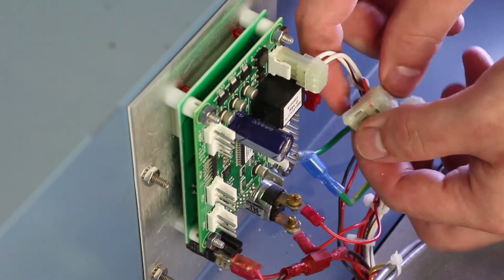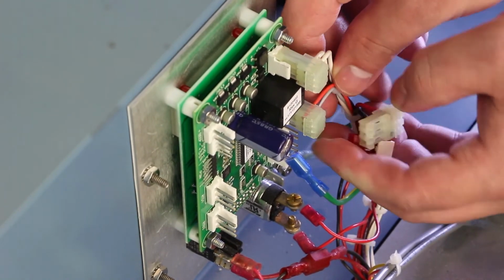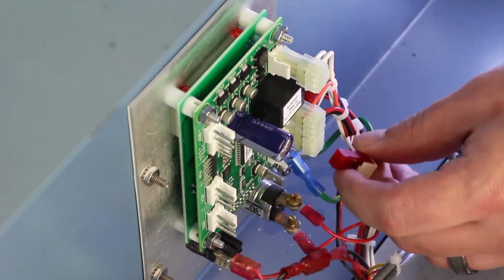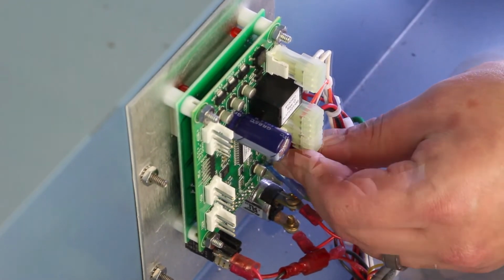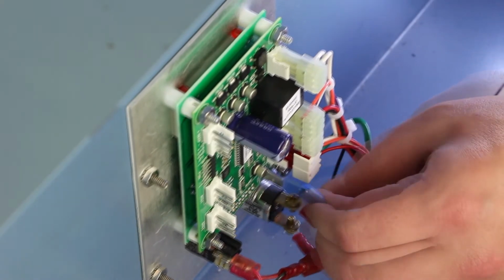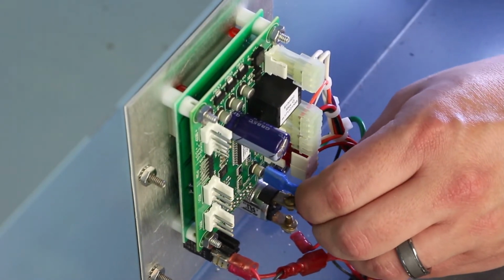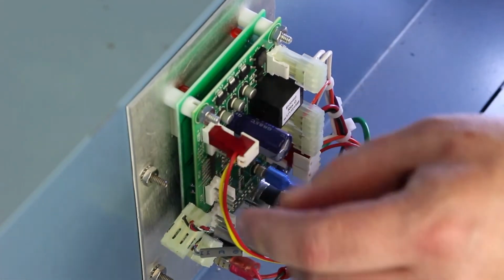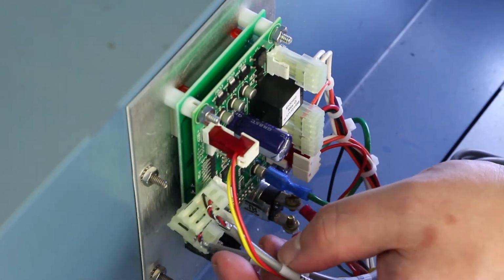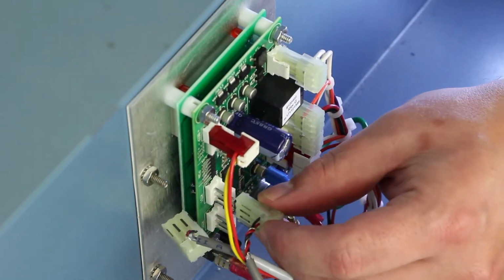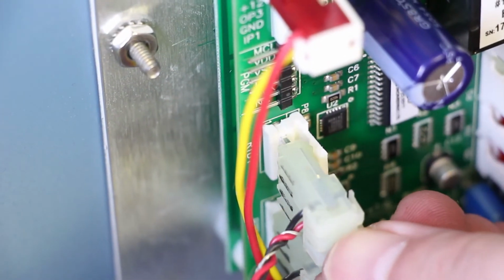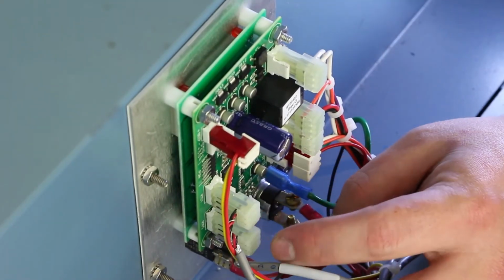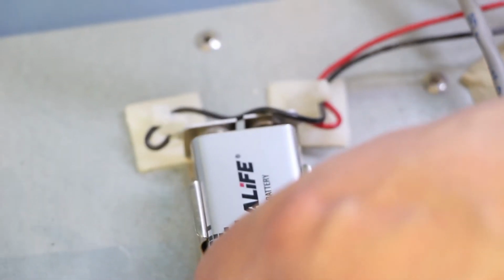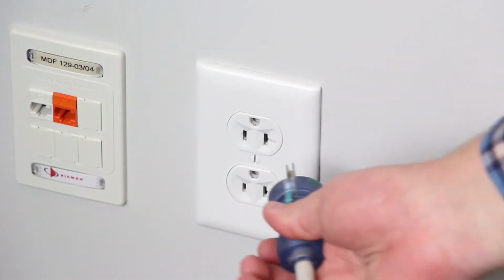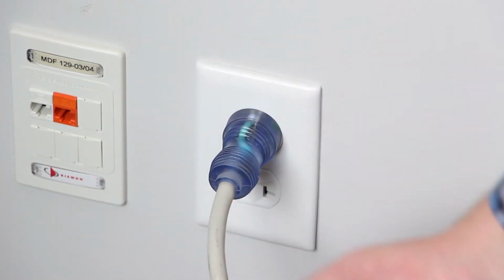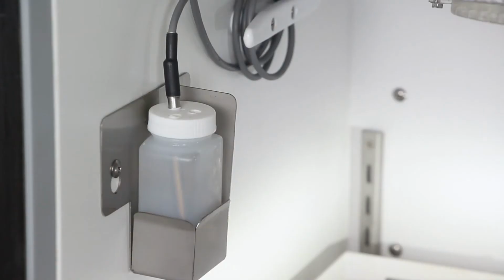Reinstall the wire connectors, making sure they are in the same location they were removed from. Pay close attention to RTD1 and RTD2 as they look identical. After the new controller is installed, reinstall the backup battery. Power the unit back on. At this point, you can program the new controller.